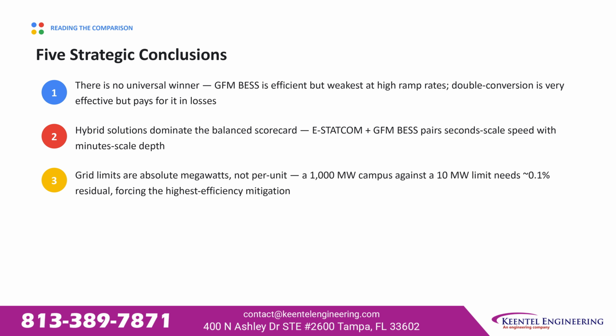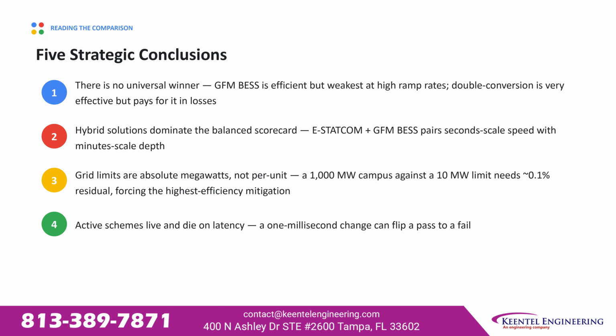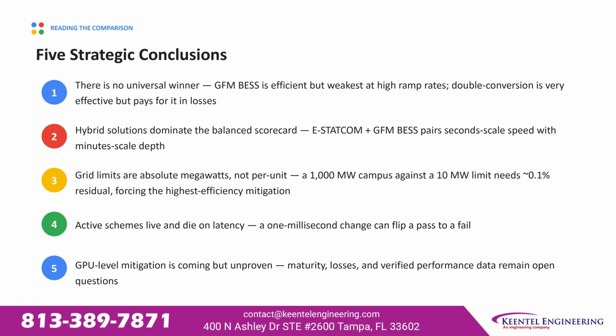Third, grid limits are absolute megawatts, not per-unit figures. A 1,000-megawatt campus facing a 10-megawatt limit needs roughly 0.1% residual fluctuation, which forces the highest efficiency mitigation available. Fourth, active schemes live and die on latency. A 1 millisecond change can flip a pass into a fail. And fifth, GPU-level mitigation is coming but still unproven. Maturity, losses, and verified performance data all remain open questions.